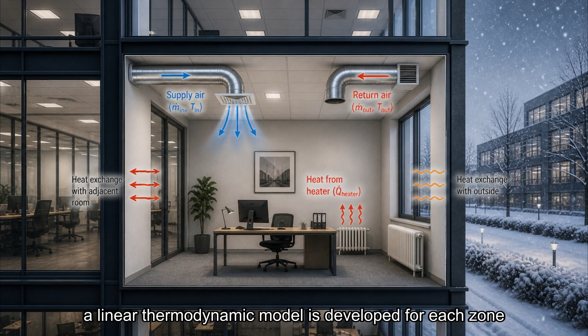In this work, a sample facility is considered, where each room is treated as an individual control zone. A linear thermodynamic model is developed for each zone, capturing heat exchange with the outdoor environment and neighboring rooms, as well as the effect of ventilation airflow and internal heat gains. The control inputs for each zone include the space heating load and the ventilation airflow rate. In addition, the supply temperature is considered as a global control variable, which is regulated by the central ventilation system.